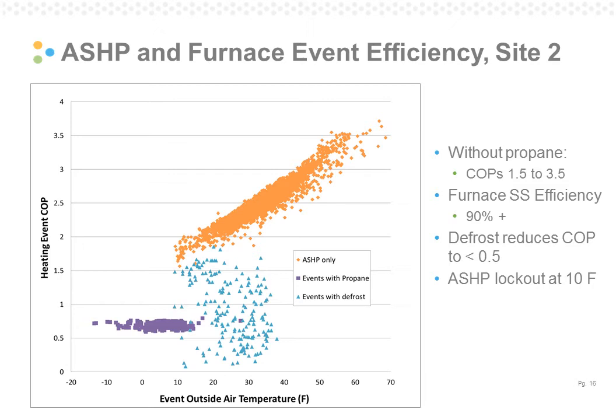And the event COP for these events is low, between 0.6 and 0.75. The blue events are heating events that include a defrost cycle at some point during the call for heat. So the defrost cycle, or the freeze protection, for anyone who's not aware, is when the air source heat pump is running in reverse to prevent frost buildup on the outdoor unit. So it's actually adding to the heat load of the home, which can drive some of the event COPs down to below 0.5.